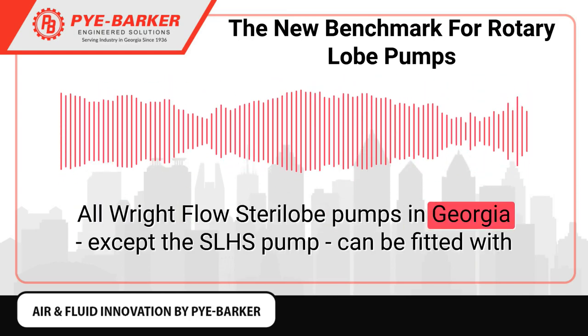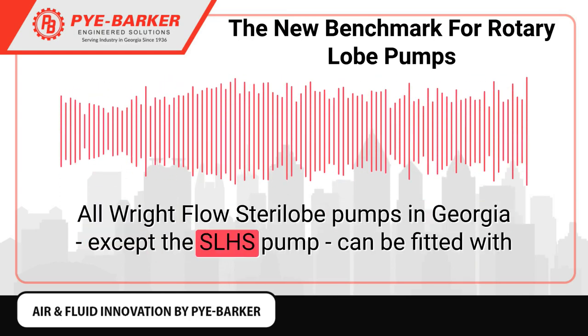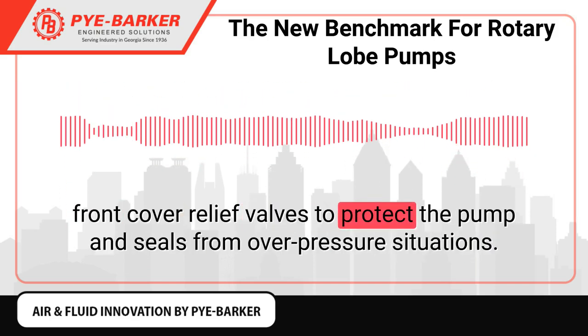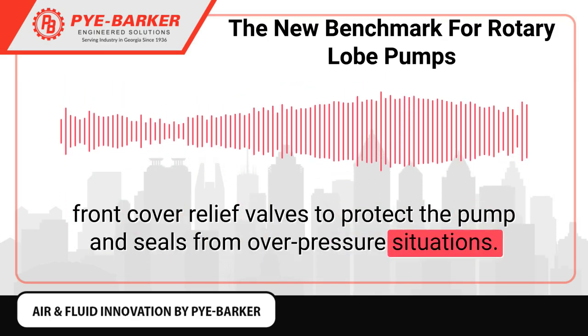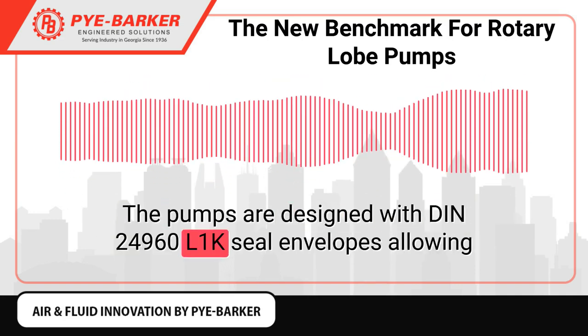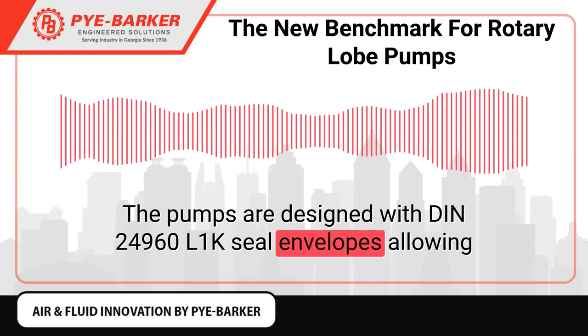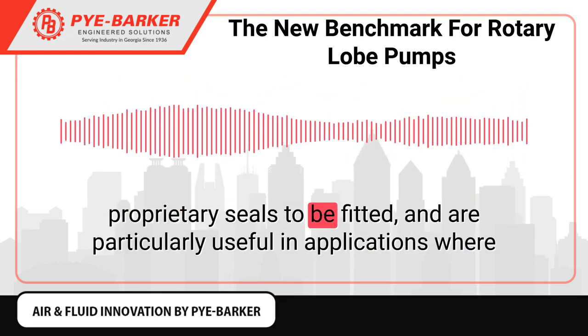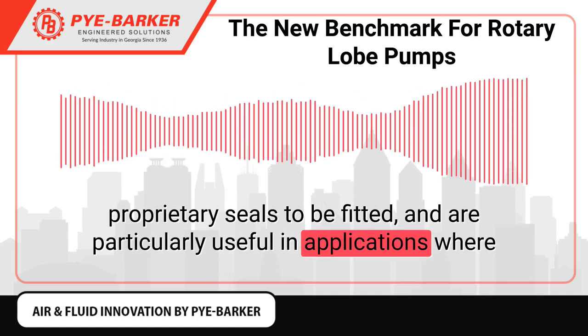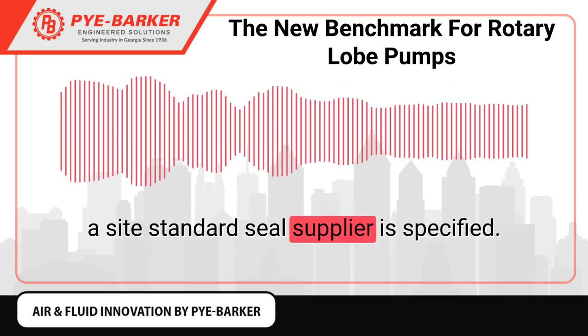All Wright Flow Sterilobe pumps in Georgia, except the SLHS pump, can be fitted with front cover relief valves to protect the pump and seals from over-pressure situations. The pumps are designed with DIN 24960 L1K seal envelopes, allowing proprietary seals to be fitted, and are particularly useful in applications where a site-standard seal supplier is specified.